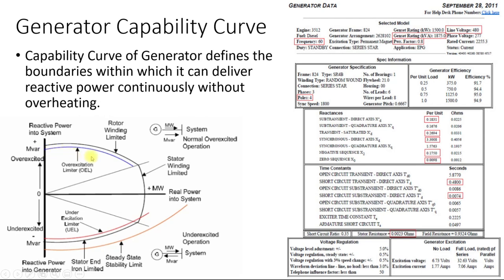In a physical generator configuration, you have a stator, and within this stator there is a rotor. On the rotor, some field winding is present, and this field winding is energized with the help of a shunt generator which provides DC current to the winding. When this DC current is provided, a magnetic field is created. The rotor is then rotated by a prime mover, and the magnetic field generated by the rotor is induced into the armature or stator, producing stator current as the output of the generator. By controlling this DC field current, you can change the value of reactive power, because you are changing the flux in the generator.